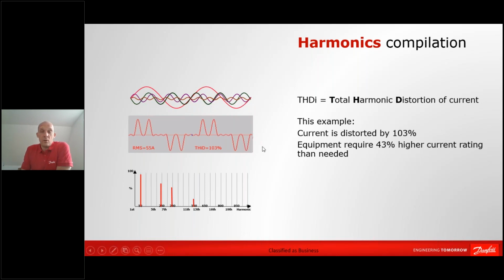To overcome this, as said earlier, we at Danfoss have always built in a DC choke, and that means that you will not see this phenomenon. You will see an RMS current that is only slightly higher than the fundamental, meaning that you don't need to oversize when you're buying a frequency converter from Danfoss. The reason for that is that we have the built-in choke inside the drive. So in order to avoid having to over-specify or over-engineer the input side using bigger cables, bigger transformers, bigger switchgears, I urge you always to buy a drive with a built-in DC choke, simply to avoid this phenomenon.